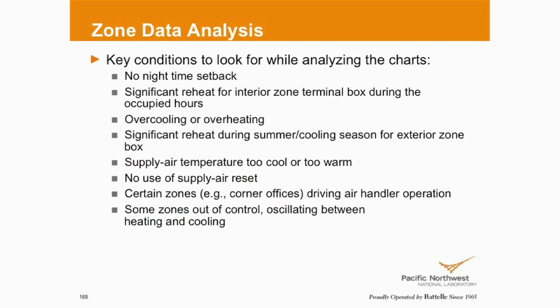And we also want to know if the supply temperature is too cool or too warm. Also, we have an interest in the zone temperature control, to see if the zone temperatures oscillate or not. Some zone temperatures may have a very narrow deadband. For example, cooling at 71 degrees and heating at 70 degrees. So if you only have a 1 degree deadband, that can cause you a lot of problems.